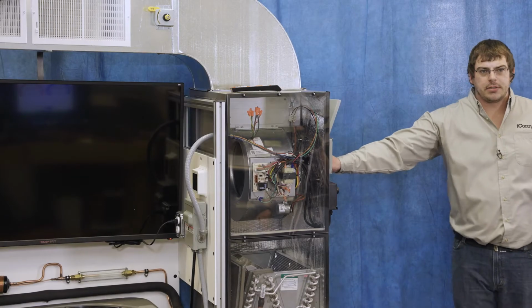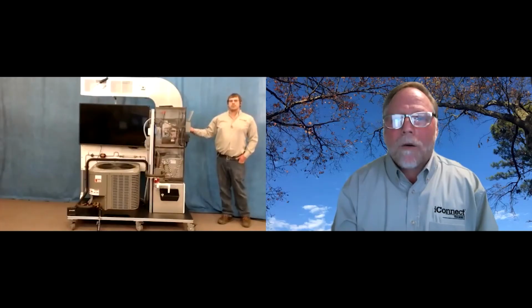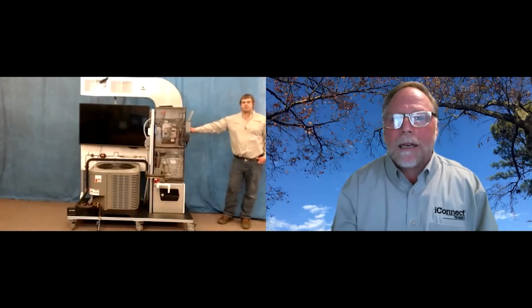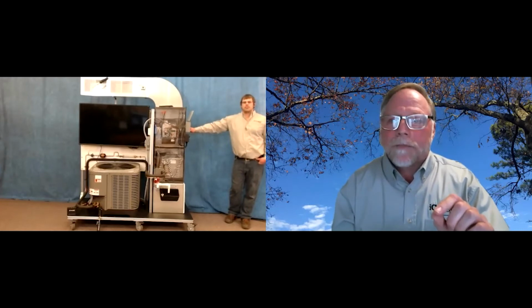So that just killed the condenser fan. All right, now watch that high side immediately start reacting to the change. This is where the students start believing what we're telling them in the classroom. And it begins to go up and up. And look at the suction pressure. At the moment, it's staying the same, but eventually it's going to start going up because we can see that the heat is not being transferred now out of the refrigerant, but it's being recycled back into the evaporator.